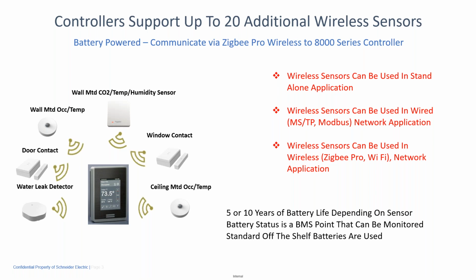So not only can you use the humidity sensor, temperature sensor, and occupancy sensor that could be built into the controller, but then again, you can add up to 20 of those additional devices if you wanted to do multiple windows, multiple doors, multiple temperature sensors to average or do a high-low signal select, or put in a water leak detector to send an alarm if there's any water. So there's many uses for these, and the nice part again is that you can add up to 20 of these sensors per controller.